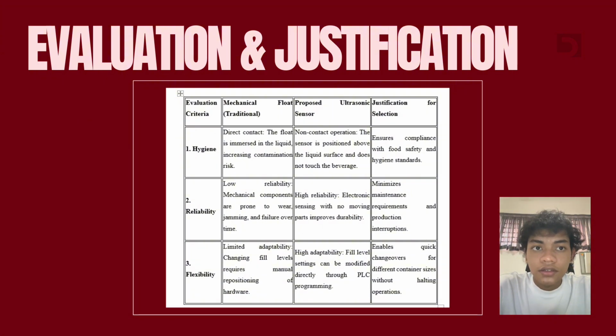First, hygiene. Traditional floats require direct contact with the product, which poses a significant contamination risk. By using an ultrasonic sensor, we achieve non-contact operation. The sensor stays above the liquid at all times, ensuring we remain in full compliance with food safety standards.